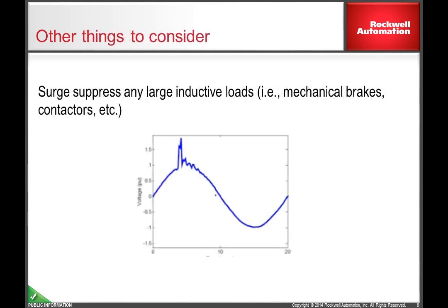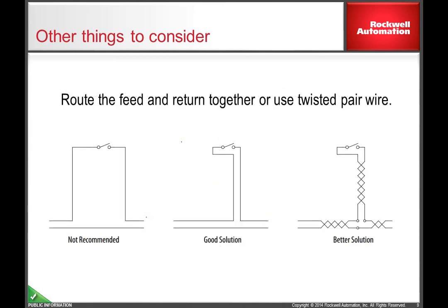Voltage transients are known to be created in an electrical system when power is applied to certain devices. These voltage transients have been known to damage sensitive equipment or negatively affect their behavior. Be sure to provide surge suppression on these devices to minimize their effect on other devices. When routing the wire, avoid creating a loop that could act as an antenna. Route the wire together or use twisted pair wire. Also, take care not to nick the insulation and verify there is no insulation damage when pulling the wire through a tight location.